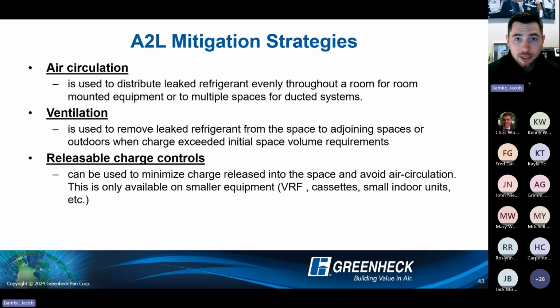So, mitigation strategies. Great. Understand that there are some things that might happen. How do I actually handle the mitigation requirements? Air circulation is the first one. Air circulation is used to distribute that leaked refrigerant evenly throughout a room, and that is for room mounted equipment, or to multiple spaces for ducted systems. So again, air circulation, let's just move as much air into these areas as we can to dilute the refrigerant.